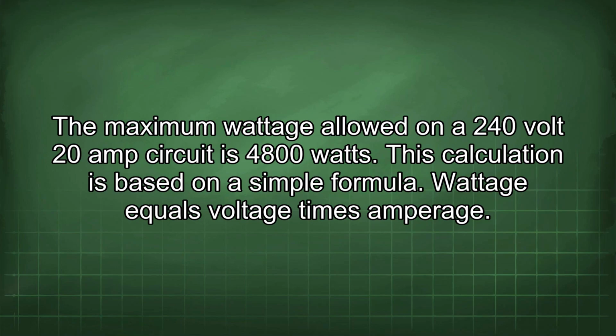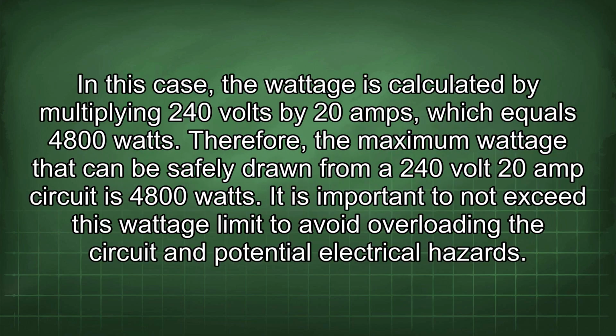The maximum wattage allowed on a 240-volt 20-amp circuit is 4,800 watts. This calculation is based on a simple formula. Wattage equals voltage times amperage. In this case, the wattage is calculated by multiplying 240 volts by 20 amps, which equals 4,800 watts. Therefore, the maximum wattage that can be safely drawn from a 240-volt 20-amp circuit is 4,800 watts.